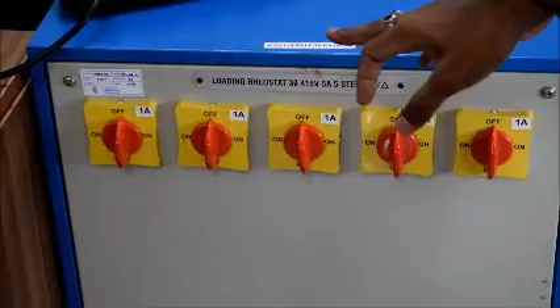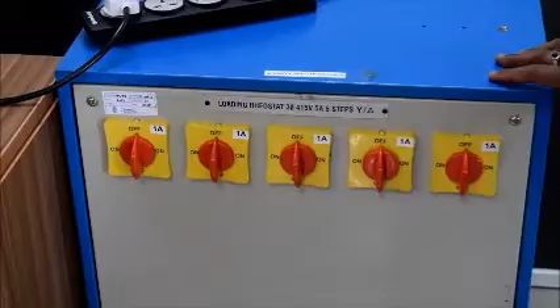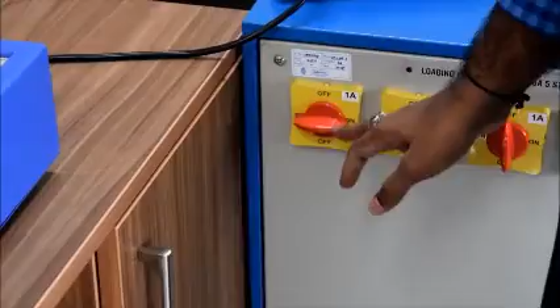Coming down to this three-phase load, as we can read here, it is a loading rheostat, three-phase, 415 volts, 5 amps, 5 steps, star or delta. This means he has given three separate coils, one each for R phase, Y phase and B phase, so we can connect this load either in star or in delta. Whenever I put in one step, it offers a loading of 1 ampere.